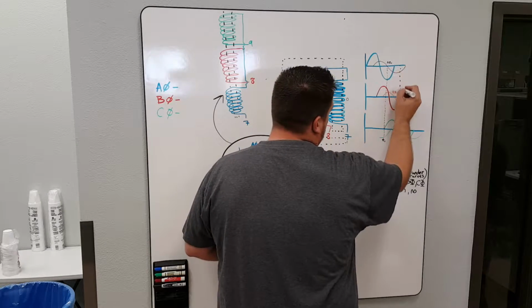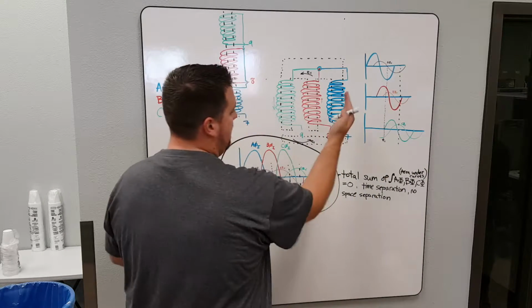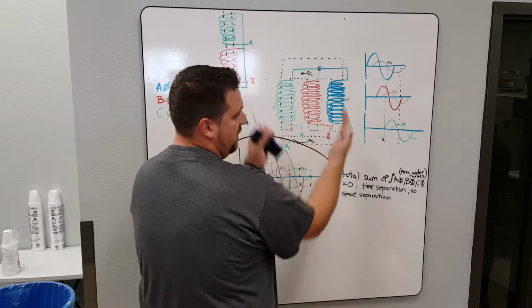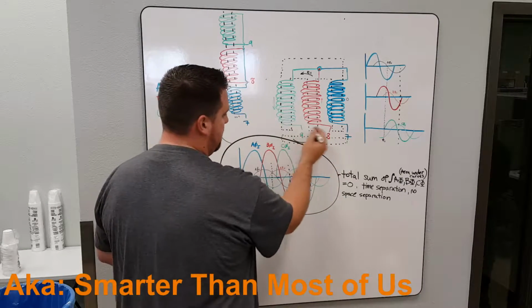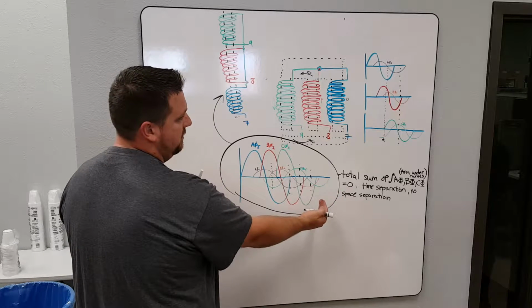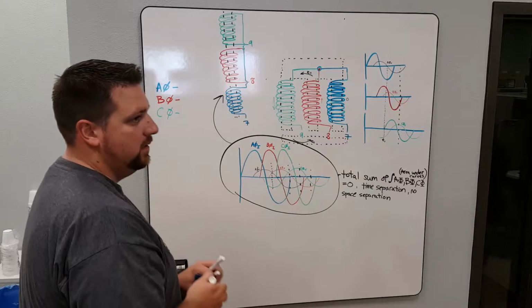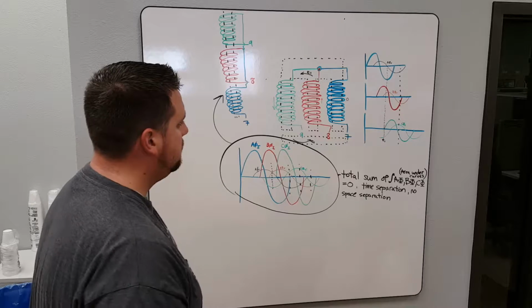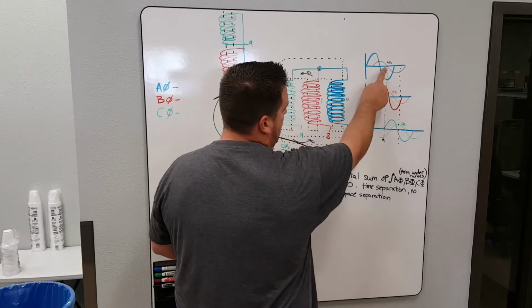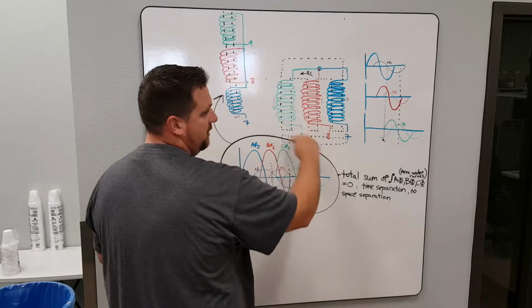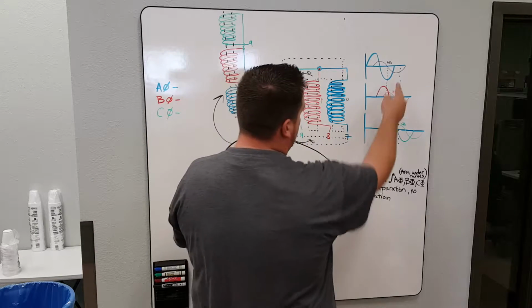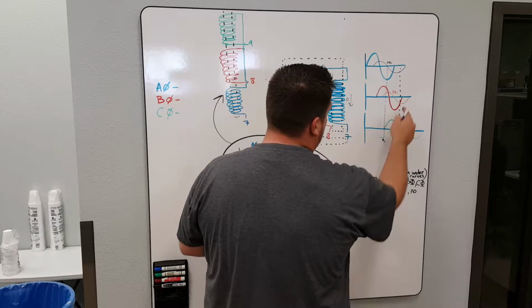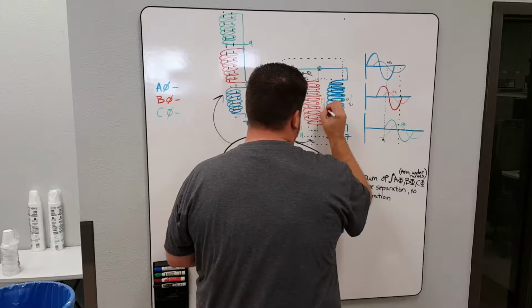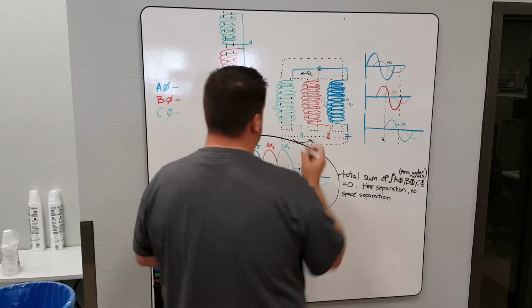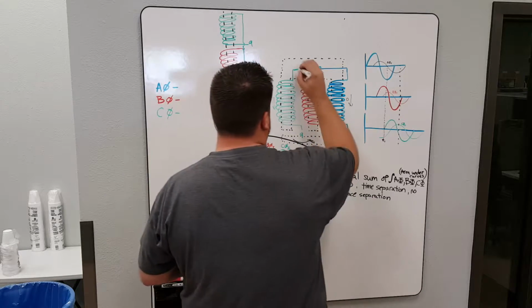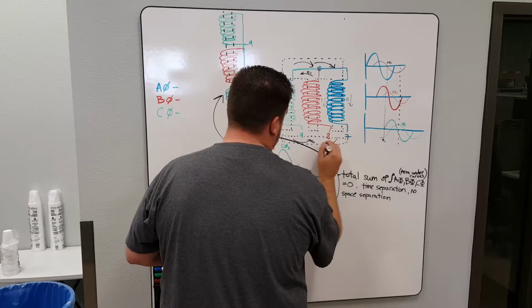Let's say at time equals 2. We'll do the same thing. Every time, with this field configuration, the flux is actually shifting between the 3 phases, but they're always going to produce a difference because they're on 3 different cores, instead of being on the same core where they all cancel out. Does that make sense? Visually, it should make it turn smoothly, as they're all going to be equal in magnitude at any point across the timeline. At this point, this is 0. This one's increasing, this one's decreasing. I've got flux set up in this direction. So let's do time 2. A phase is decreasing, C phase is decreasing, and I've got B phase increasing at almost the max. So I've got a field that's set up in a new direction at time 2.